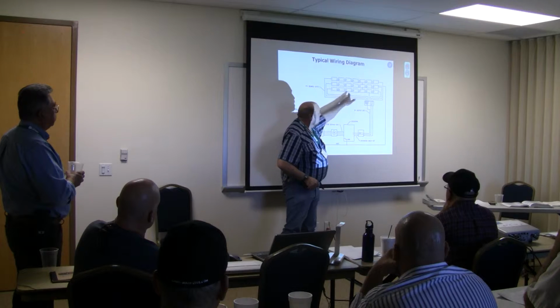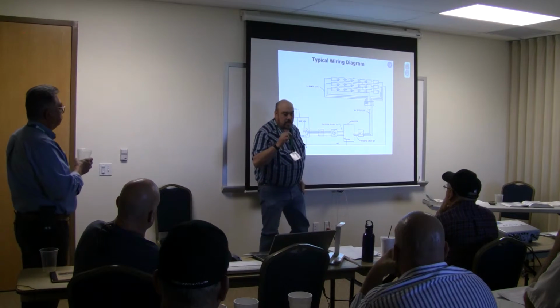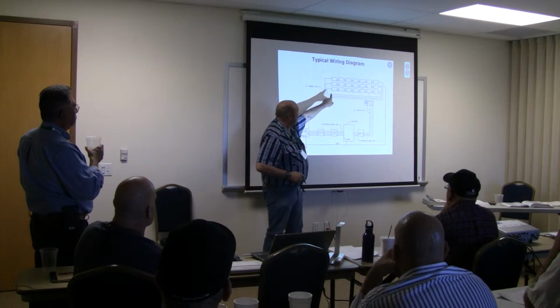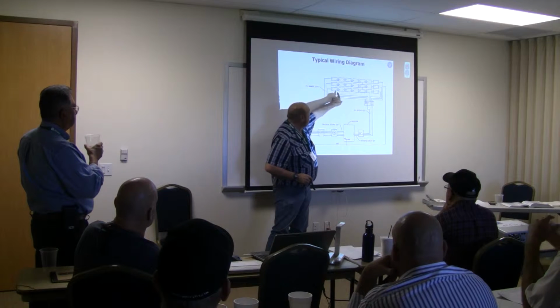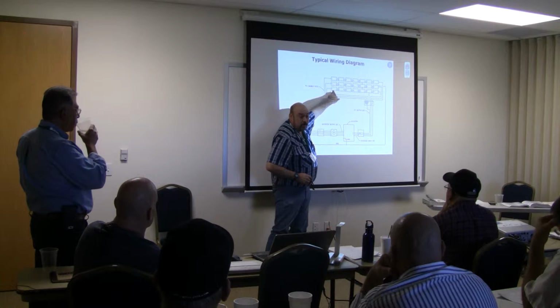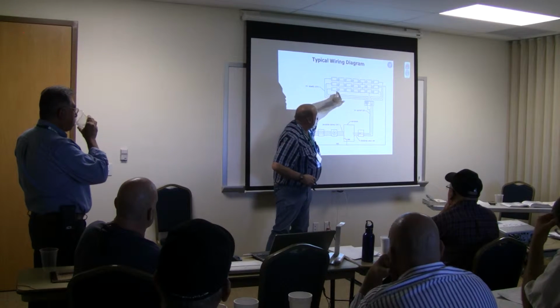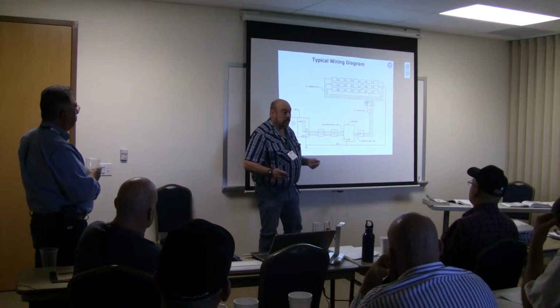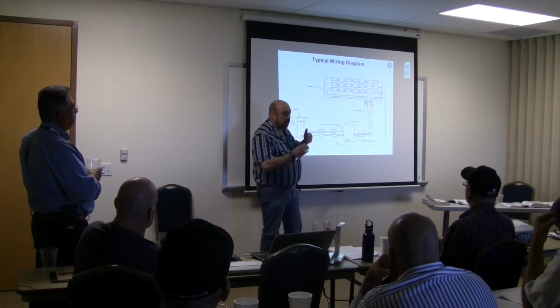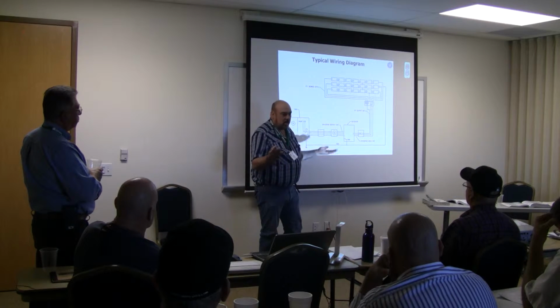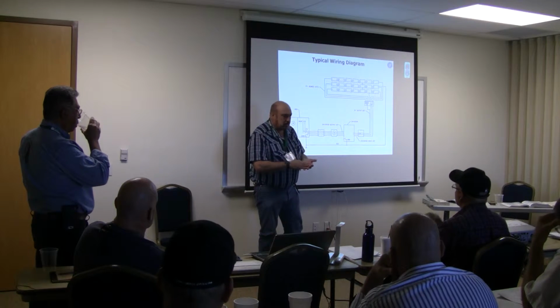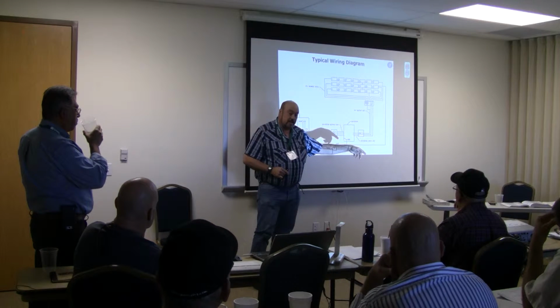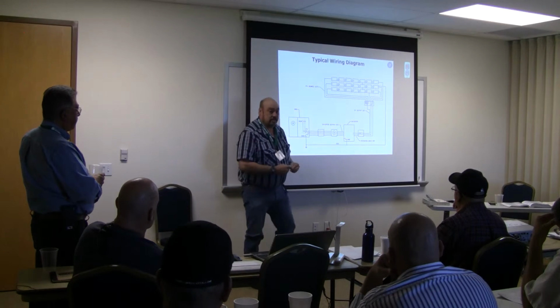So you're going to count the number of these modules, and you're going to multiply it by the VOC of, say, this was 37.4. Okay? So we don't want to exceed 600 volts ever. So you're going to calculate that up, whatever that number comes up to, then you're going to go to Article 690.7. There's a table at 690.7.